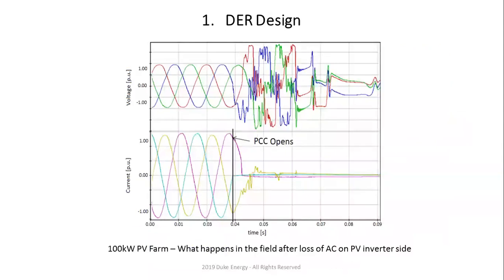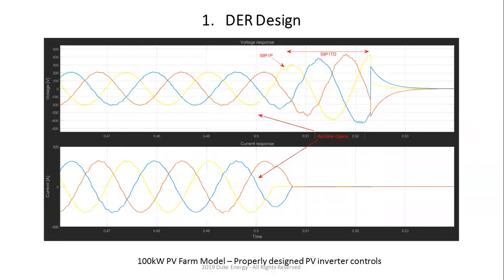Which means that within the microgrid that you're trying to put in, the PV system on its own cannot sustain the microgrid, right? Again, it has to have IEEE 1547 and UL 1741 certification. If they don't have those certifications, your models can produce what I just showed you, right? So essentially what happens over here is that as your voltage goes down, the inverter detects the under voltage when you open the PCC, and it tries to overcompensate. So it pushes the reactive power so that the voltage goes above. The 59 is the setting for the over voltage, and after 160 milliseconds, it trips.